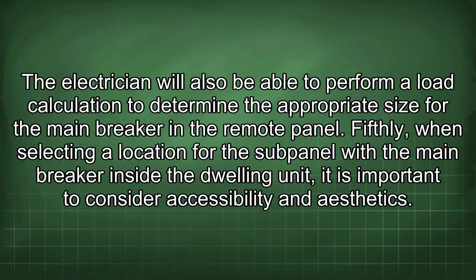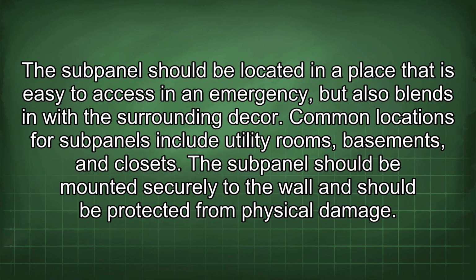Fifthly, when selecting a location for the subpanel with the main breaker inside the dwelling unit, it is important to consider accessibility and aesthetics. The subpanel should be located in a place that is easy to access in an emergency, but also blends in with the surrounding decor. Common locations for subpanels include utility rooms, basements, and closets. The subpanel should be mounted securely to the wall and should be protected from physical damage.